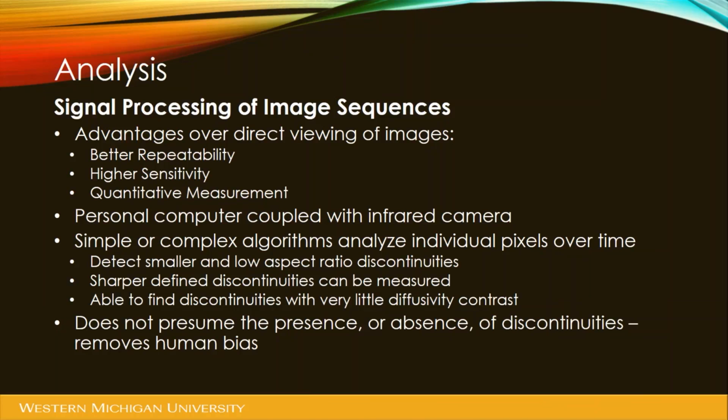We look at these pictures that have color, right? If you've got two pixels next to each other that are 0.03 degrees Celsius different, do you think there's going to be much of a color difference on the picture we look at? Not unless you shrink your color range down really far. Computers, though, can pick out that one's 1.000, that one's 1.003, that one's 1.006, that one's 1.009, and then that one's 1.08. There's one oddball in the middle here, what's going on, right? A computer can pick that up.